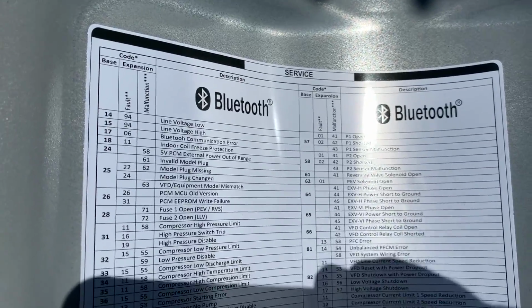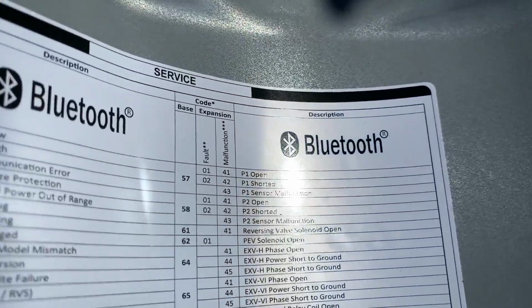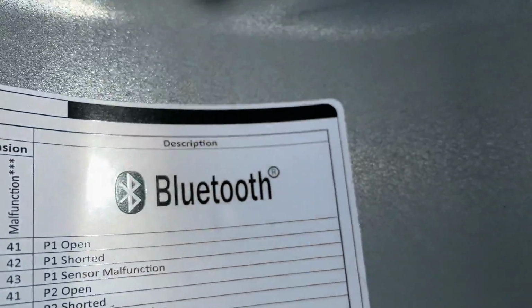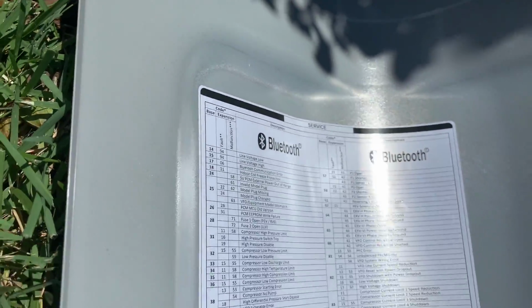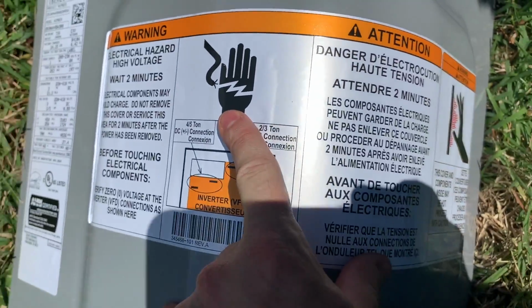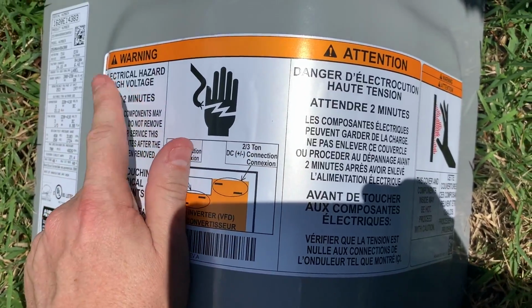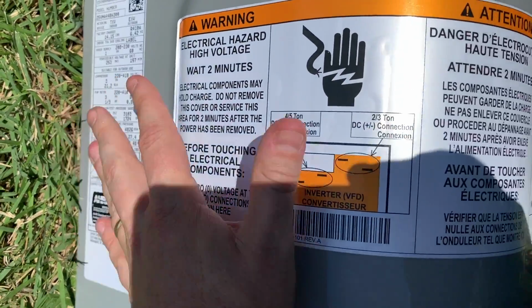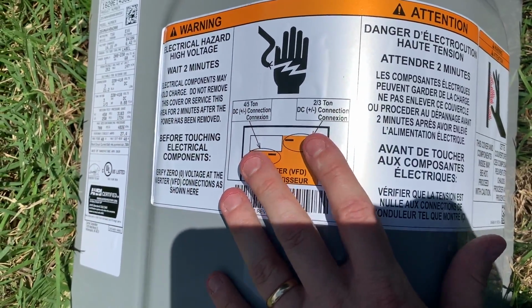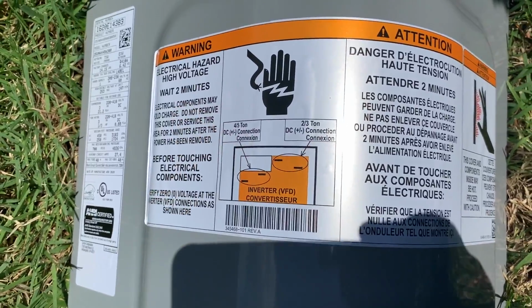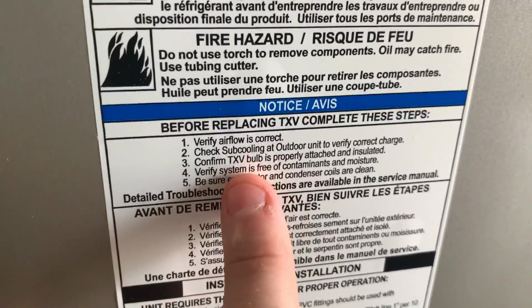Bluetooth diagnostics in it. So you can walk right up to it and see any errors that you may have right from your device. Be super careful when you're dealing with inverter driven equipment because you have much higher voltages. So once you disconnect power and you confirm that it's disconnected at the disconnect, wait 2 minutes before taking the panels off.